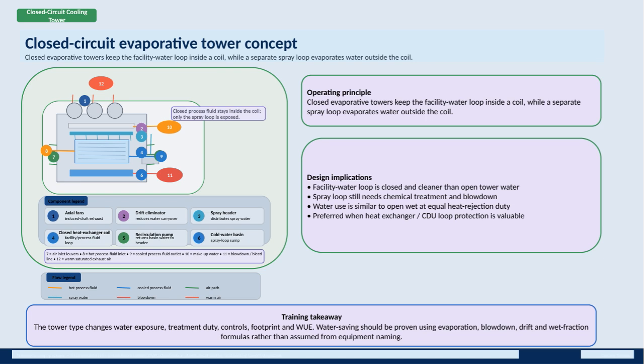From a design perspective, this closed loop offers significant advantages. The process fluid is protected, reducing contamination risks, while the spray loop still requires chemical treatment and blowdown to manage water quality. Water consumption is roughly similar to an open wet cooling tower when performing the same heat rejection. These towers are preferred when protecting heat exchangers and cooling distribution units is critical. The training takeaway here is to understand that the cooling tower type directly affects water exposure, the required treatment, operational controls, footprint, and water use efficiency.